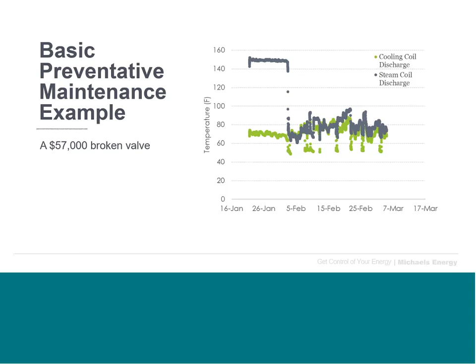So that likely had been operating that way for years, and because nobody had specifically looked at whether their valves had any problems, they were basically running their cooling system to offset the amount of heat that was being put in by their steam system. And when we did the math, it came out that was about a $57,000 annual cost for them. So that's a little on the extreme side. Many places won't have equipment that's quite that large, or wouldn't make that sort of thing more obvious, but there's certainly places where that can have such a huge impact. So little things like a single steam valve can have massive impacts on a piece of equipment.